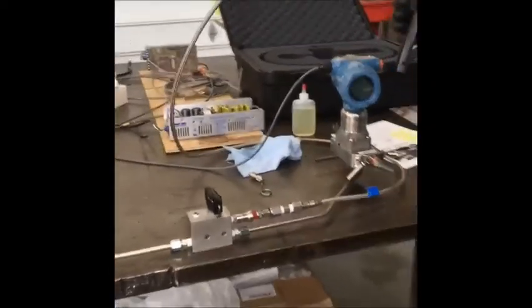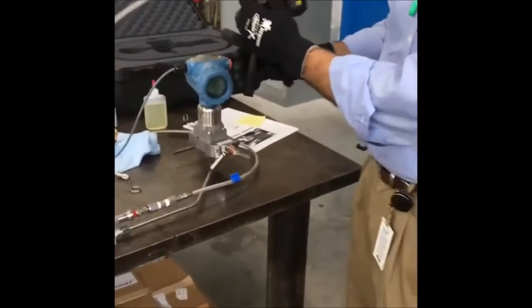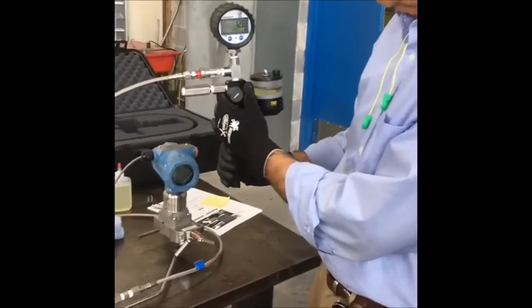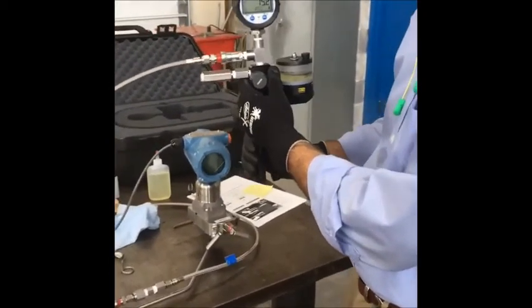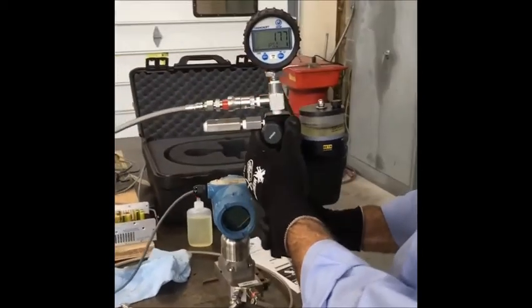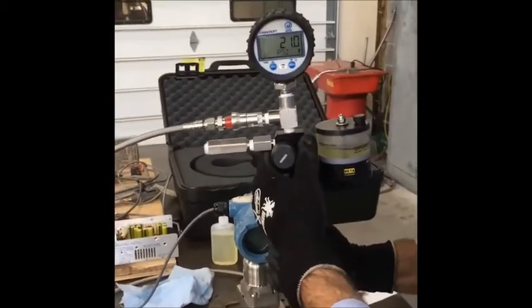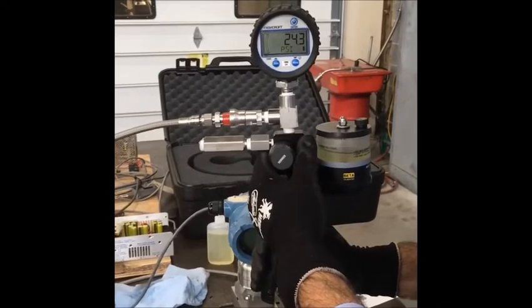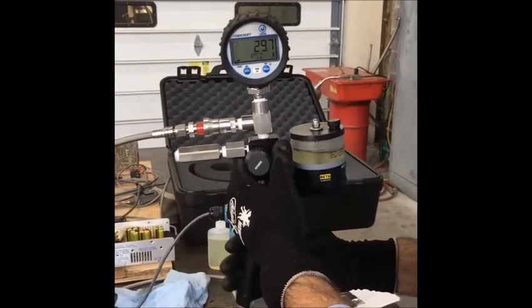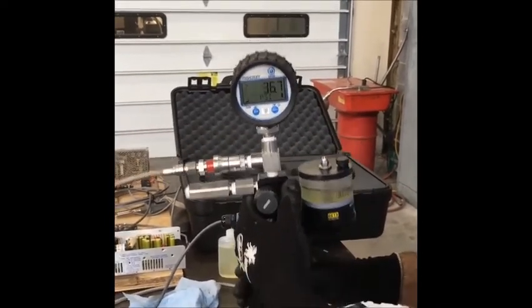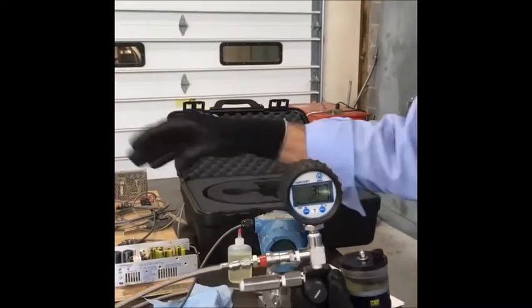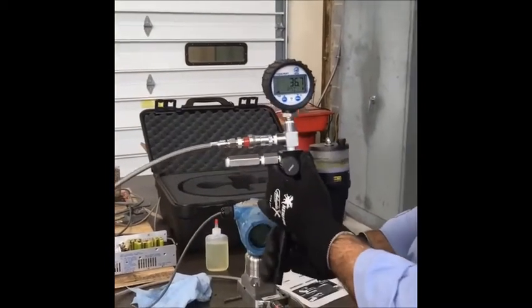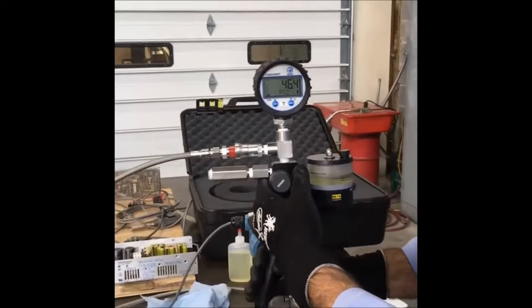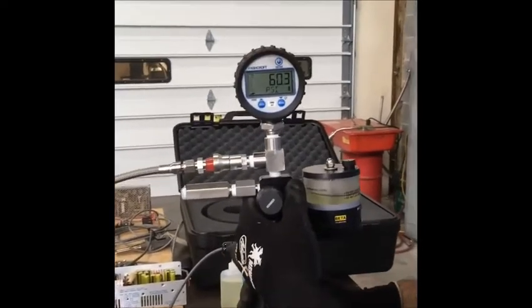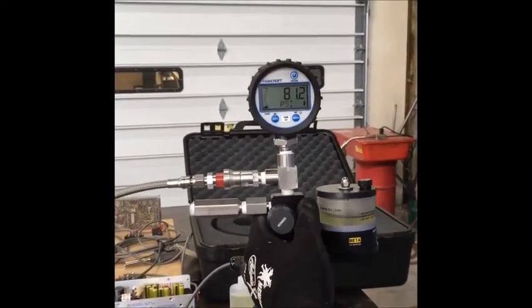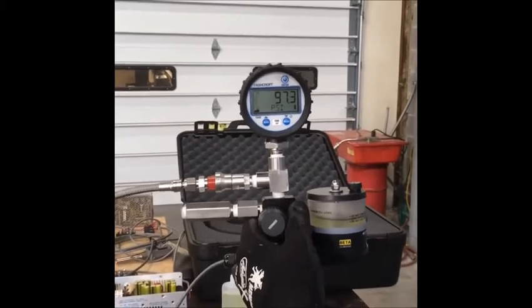Now as we start to do our calibration and we start to pump up with oil pressure, we will build pressure until we come up to the point that we equal the system pressure, and at that point then the calibration pump will start to take the high pressure cutout above the system pressure, but not until we get up to that level. So you can see with each pump I come up a little higher. I'm about 80 pounds now.